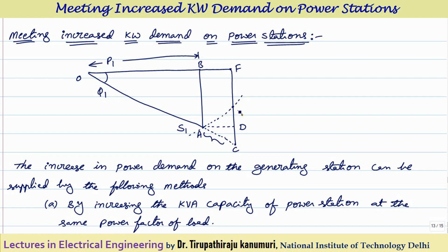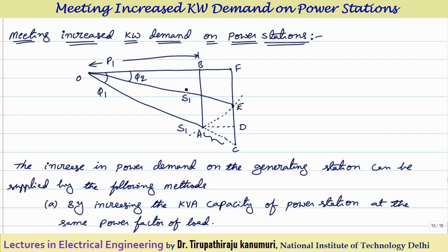Your circle will intersect at this point. That means with the same S, you have to improve the power factor up to a certain level. Using this approach, if the power factor is improved to phi 2, this point is represented by E, and OE is equal to S1 — the same KVA. We can maintain the same KVA by installing power factor correction equipment and still supply the required load. For a given KVA rating, the power plant can supply more power if the power factor is improved.